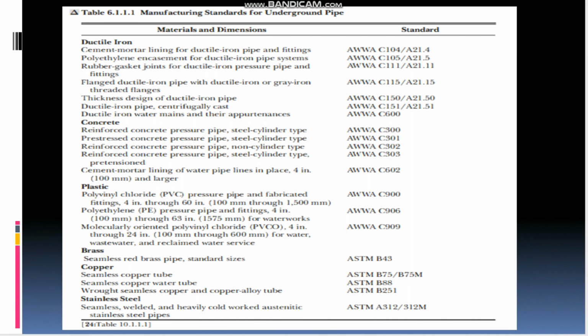So here in Table 6.1.1.1 from NFPA 13, different types of approved underground pipe material are given, like ductile iron, concrete, plastic, brass, copper, stainless steel, different things you can see here. When it comes to polyethylene pipe, from 4 inch to 63 inch for underground pipe, it has to follow this standard.